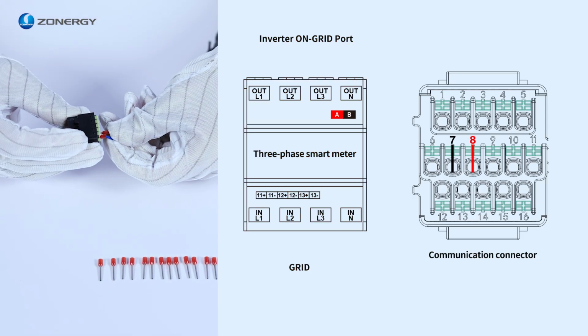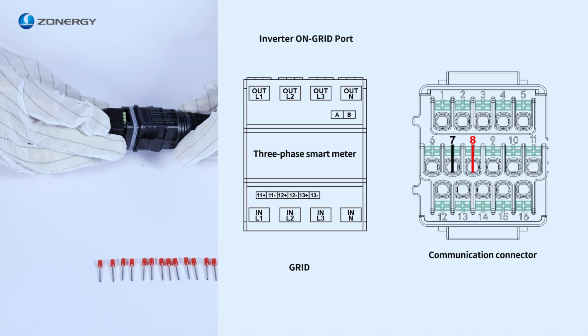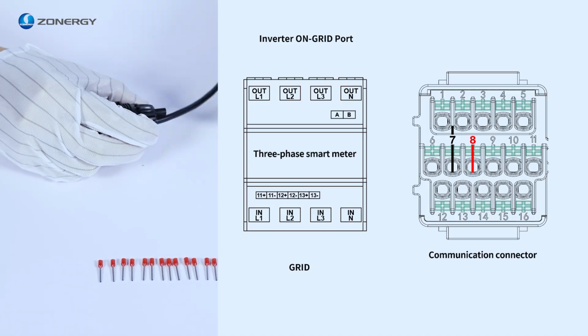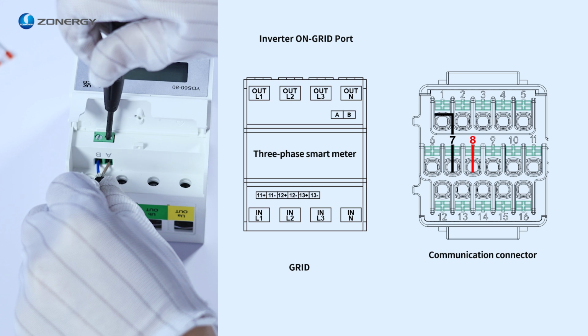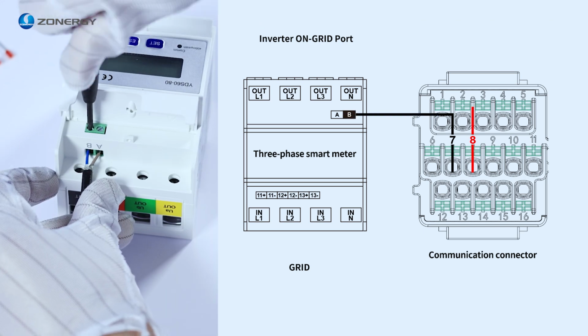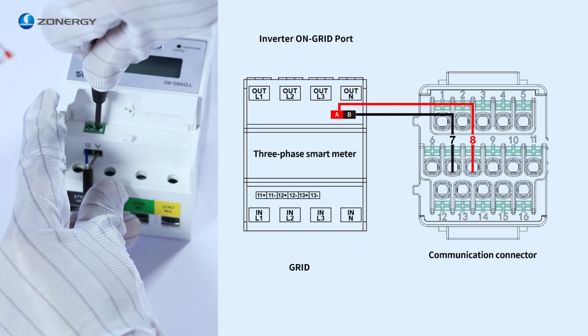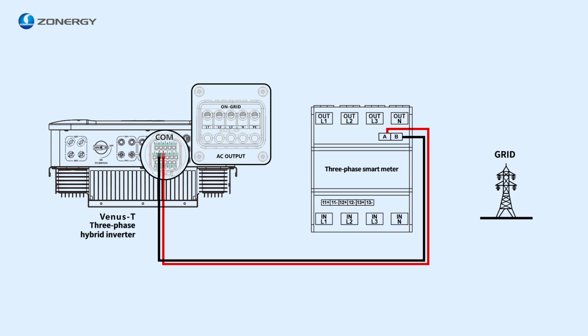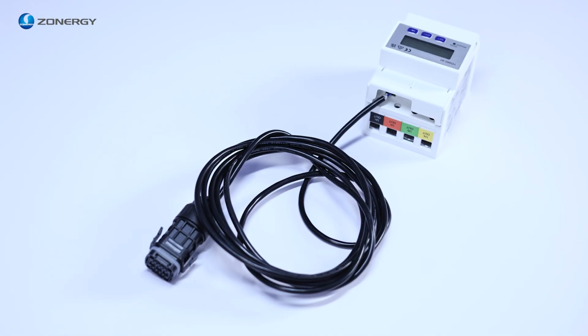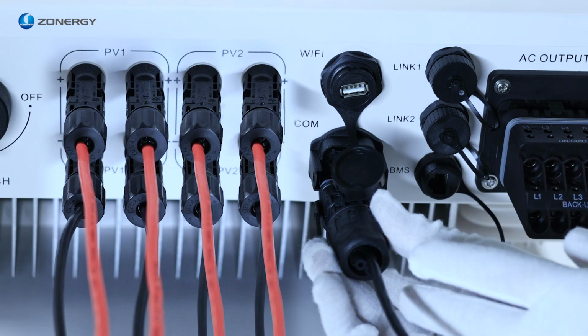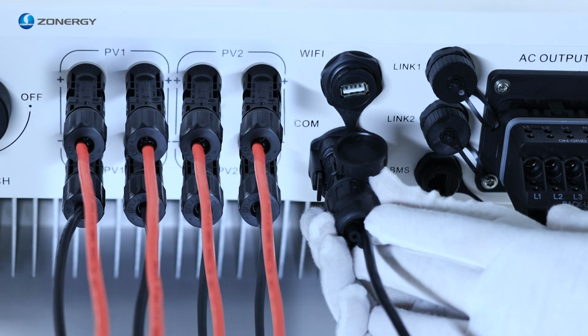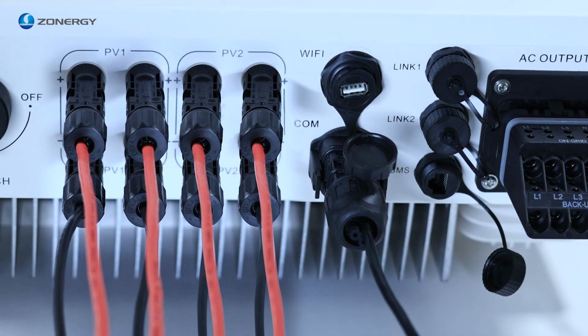5. Confirm the 2 ports A and B of the 3-phase smart meter. Connect the port 7 cable on the communication connector to port B on the meter, and connect the port 8 cable to port A on the meter. The following is a prepared communication terminal. 6. Connect the prepared communication terminal to the inverter communication port.